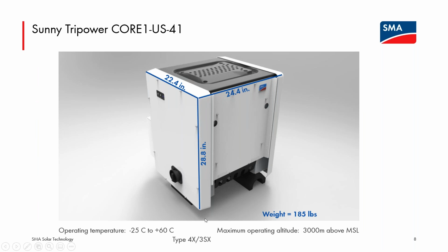I don't want to spend too much time on the inverter, but you have some dimensions here. You see the rating. The operating temperature I'll talk about briefly because I think certainly in areas of Canada, the low end of the operating temperature is of interest to folks. The operating temperature goes down to -25 C. The safe exposure temperature for the CORE1 goes down to -40 C. But if the inverter wakes up between -40 and -25, it will wait to go into operation until it achieves the -25 C temperature. And there's a very specific error code you'll see, waiting for minimum operating temperature, until that -25 C level is hit.